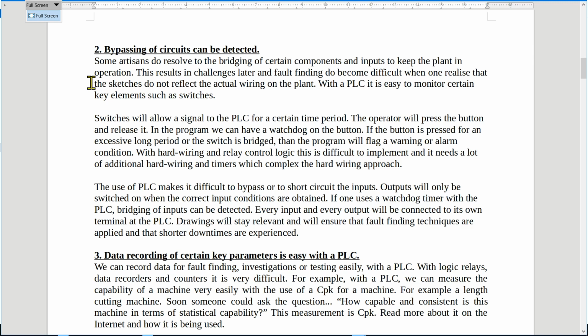With a PLC, it's easy to monitor certain key elements, such as switches. Now, switches normally will allow a signal to the PLC for a certain time period. The operator will press the button and release it, for example, to start the machine. In the program, we can have a watchdog on the button. If the button is pressed for an excessively long period or the switch is bridged, then the program will flag a warning or alarm condition.